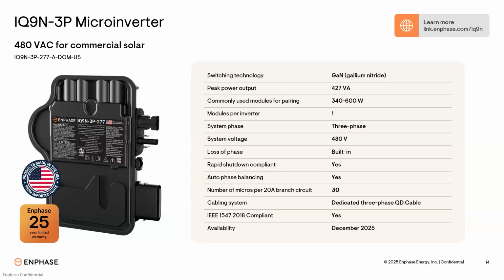Our system is 1 micro per 1 module. It is 3-phase, 480 volt. It has loss of phase built in, as well as rapid shutdown. It is auto phase balancing, and you can put up to 30 of these micros on a 20 amp branch circuit.